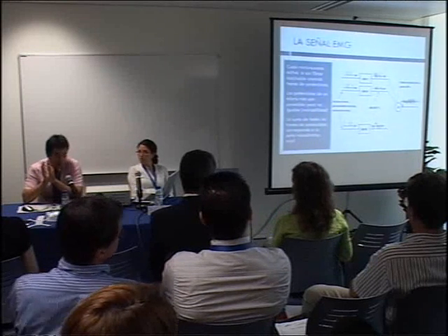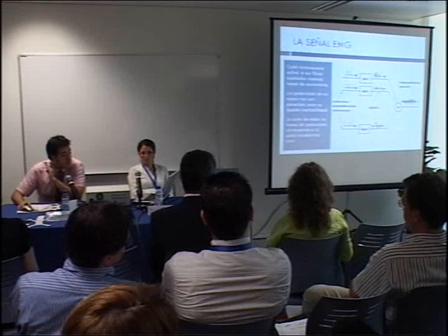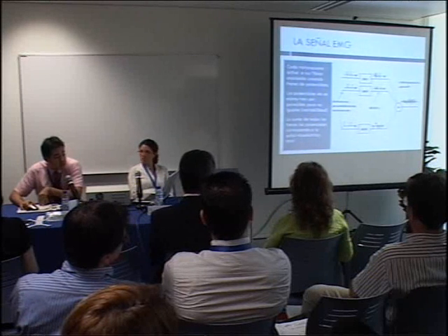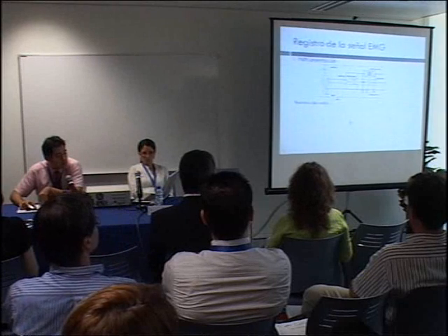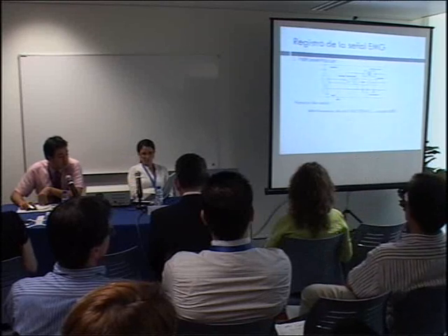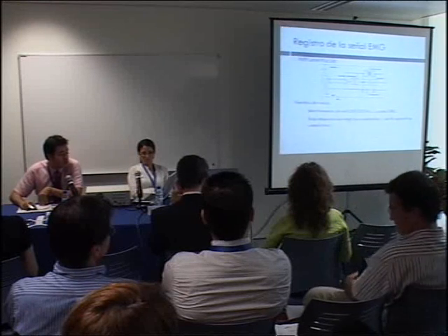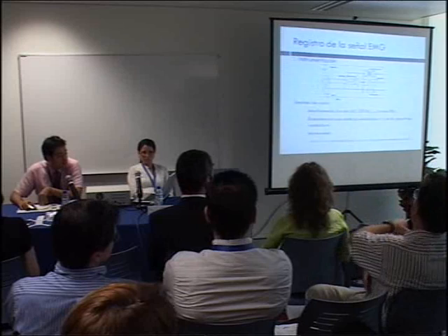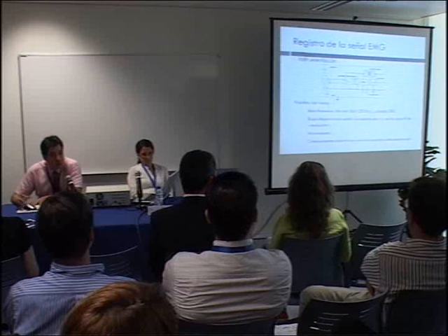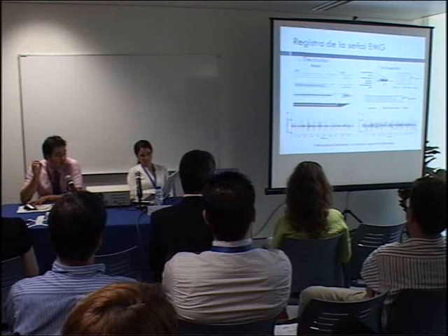In view of this, one of the applications we'll be looking at is to try and go back, i.e., from the basis of this recorded information, to try and detect how many motor units are active and when they have been activated in the course of time. So recording the EMG signal, as is the case with any biological system, has problems. For instance, interference from the mains, high impedance between electrodes and conductive surface, movements, electronic components in the instrumentation system. So you need to do some pre-processing.